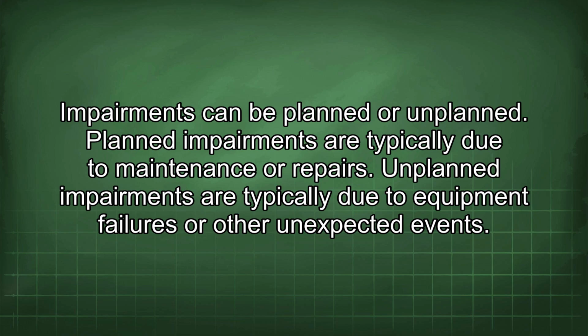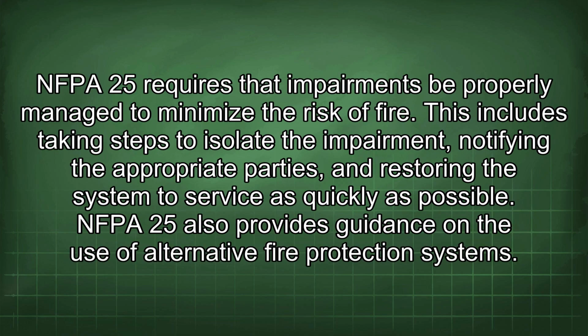Impairments can be planned or unplanned. Planned impairments are typically due to maintenance or repairs. Unplanned impairments are typically due to equipment failures or other unexpected events. NFPA 25 requires that impairments be properly managed to minimize the risk of fire.